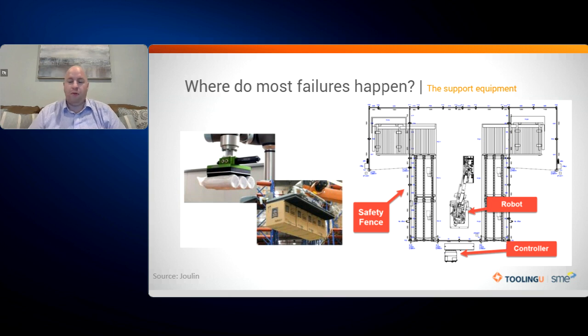Maybe if you're also setting up a robot, I have seen this scenario before, make sure that you guys are using liquid anchors when you're affixing the robot to the floor. There should be within the guide of the robot how to appropriately affix it to the floor. And I've also seen when you do mount them to the floor, the threads that are popping up, do people a favor and cut the threads probably within maybe a half an inch of the nut so that you don't have issues of people hurting themselves when they're walking around the pedestal. These are all just general maintenance items that should be looked at.